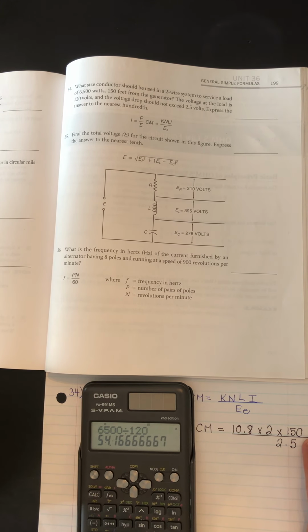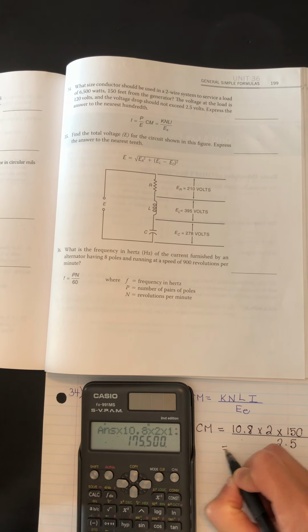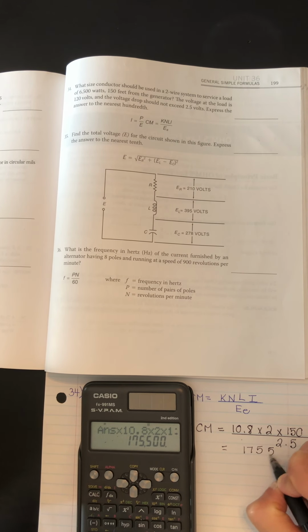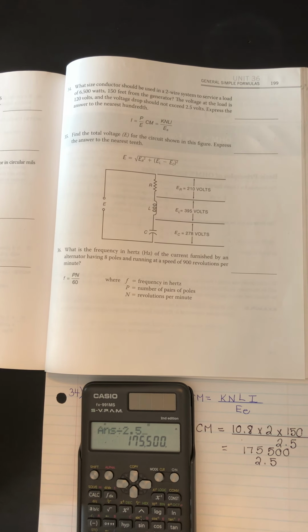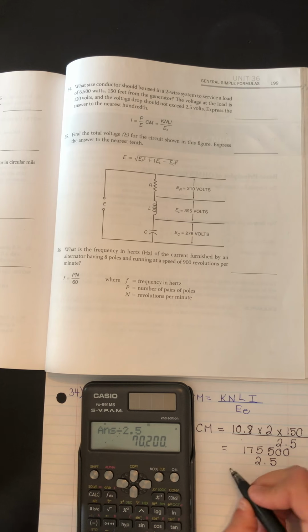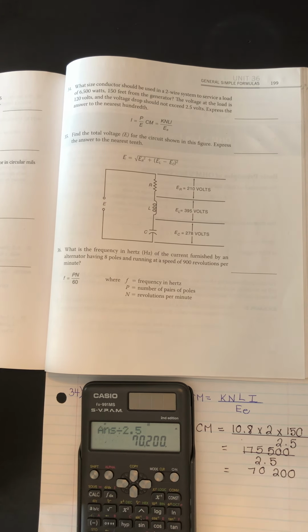Okay, so I'm gonna multiply it by 10.8 and by 2 and by 150. Okay, so that's my numerator now. And I'm going to divide it by 2.5. And we get our answer, 70200. So that represents the size of the conductor. And this would be in circular mills.